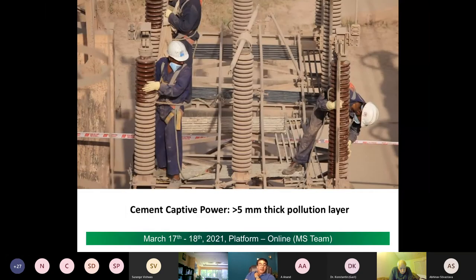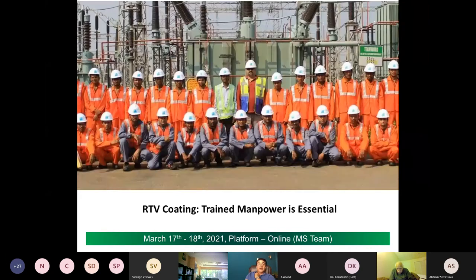Here is cement in a captive power plant. You can see there is 5 mm of pollutant layer, which is a major issue for hydrophobicity to transfer. But here they're cleaning the layers of limestone related mud off the insulator before the coating. Even here, it has been used for many years with no failure.